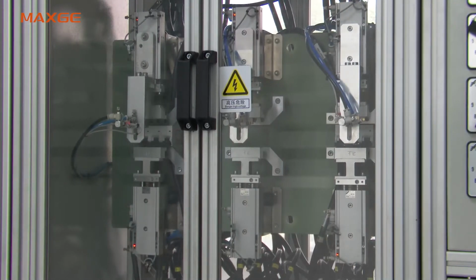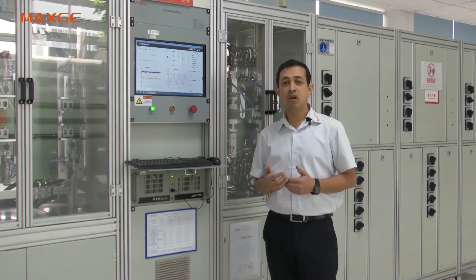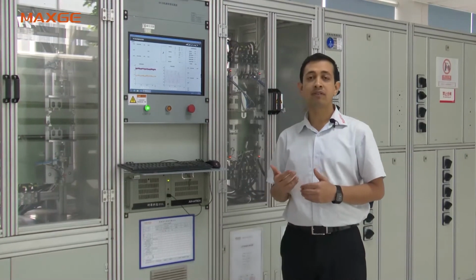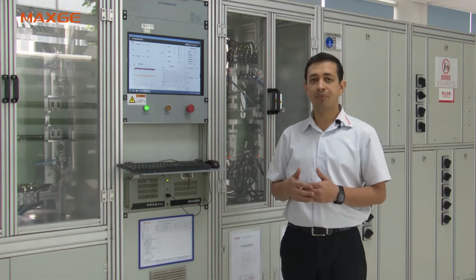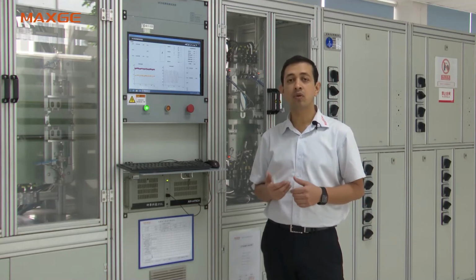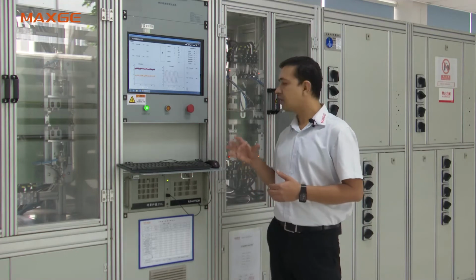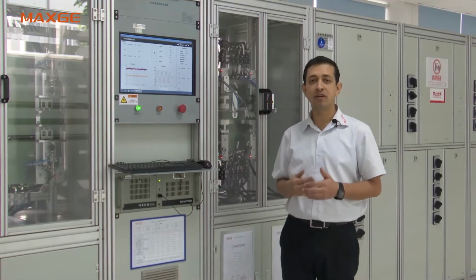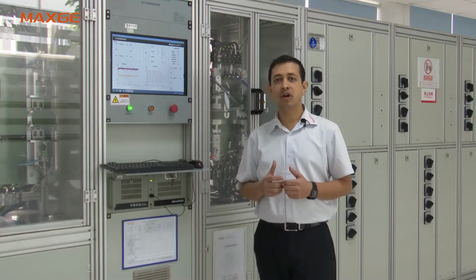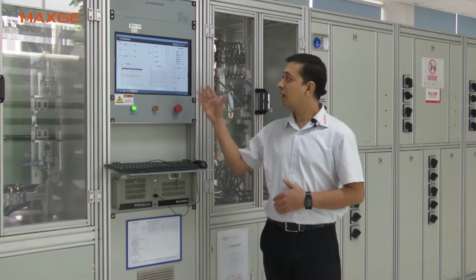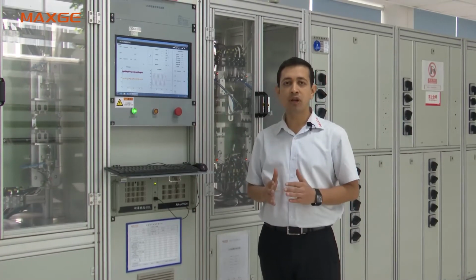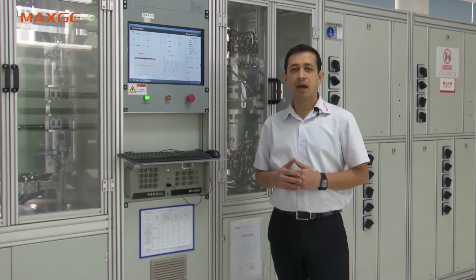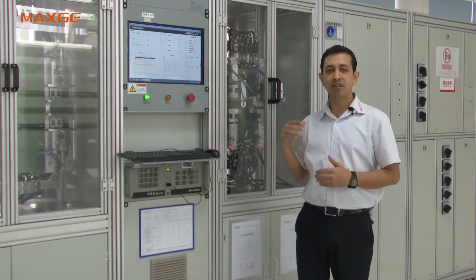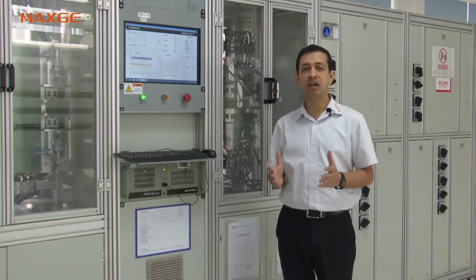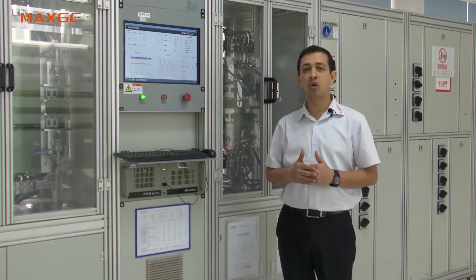Our MCB qualifies over and above the standard levels. For example, the MCB qualifies around 10,000 electrical operations, wherein the standard says only 4,000, and for mechanical endurance, it qualifies for 20,000 mechanical operations. Our MCB and MCCB designs are very sturdy and we use good quality silver graphite tips, so we can ensure that the electrical endurance test is qualified for every lot, and that whenever this MCB and MCCB goes to the field, it can perform at the highest level and serve for a longer life.